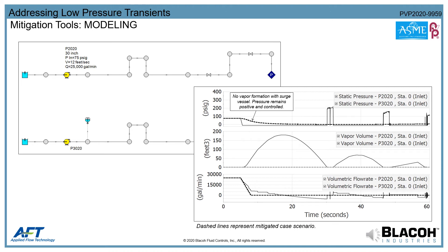In this application, computer surge modeling was used to help protect a fuel terminal loading facility in the U.S. Gulf Coast region. The project entailed a 30-inch carbon steel line over 3,000 feet long, designed to carry fuel from a plant to a shipping loading terminal, including a 20-foot elevation change to clear a railroad. The pump generated 25,000 gallons per minute at a velocity of 12 feet per second and a discharge pressure of 75 psi. The surge analysis predicted the system would go into full vacuum with cavitation imminent, and engineers used modeling software to size and place a surge vessel.